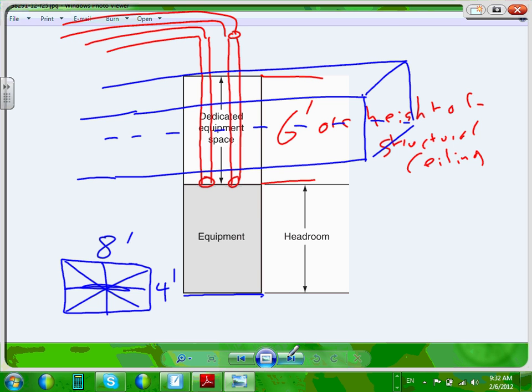So here's my dedicated space. Can I put a big fat duct here? Yes, as long as there's protection from leaking. They don't want you, guys, mechanical equipment rooms are extremely busy. They don't want you to put a water pipe right above the switchgear and that water pipe starts leaking. Not in the dedicated spaces, above the dedicated spaces. They try to avoid it unless you have some type of protection against leakage of this water pipe over my electric equipment. So the rule is to avoid putting anything mechanical right above the equipment. If you have to, then you have to prove to the electrical inspector what happens if there's a leakage.